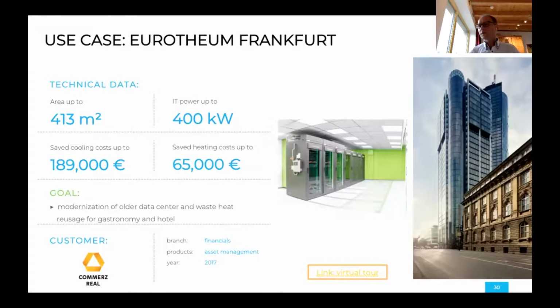One more famous use case is the Eurotower, the skyscraper in Frankfurt, which was the home of the European Central Bank for almost 10 years. The central bank moved out of this skyscraper, and they allowed us to take over the infrastructure data center in the building. The 7th floor and an underground floor held a fully replicated data center infrastructure, but it wasn't very energy efficient - it was cooled by massive air conditioning systems on the roof, which with the new hotter summers came to its limits.